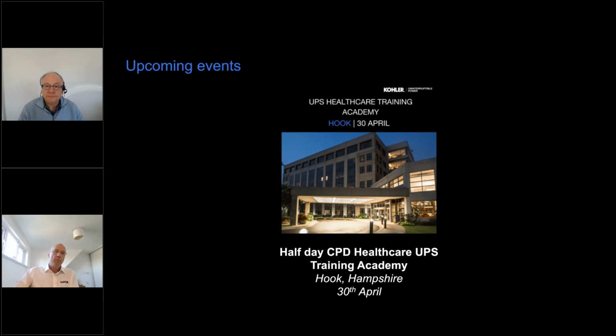Okay. Most UPS manufacturers are fighting to get the most efficient UPSs out there. That's one thing, to make sure that we only use the amount of energy that we need to use. So we're looking at over 97% online efficiency for a lot of UPSs, making sure we use as little energy as we can. The UPSs do have eco passports. Many manufacturers are making sure we have an eco passport for the UPSs, to make sure that it is made sustainably in the factory to start with, and then it has a life cycle and recyclable part to it.